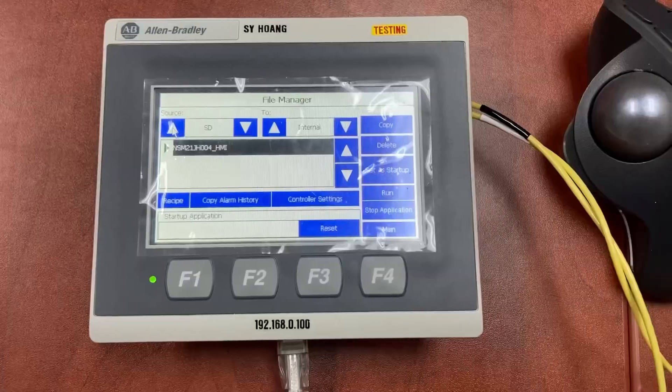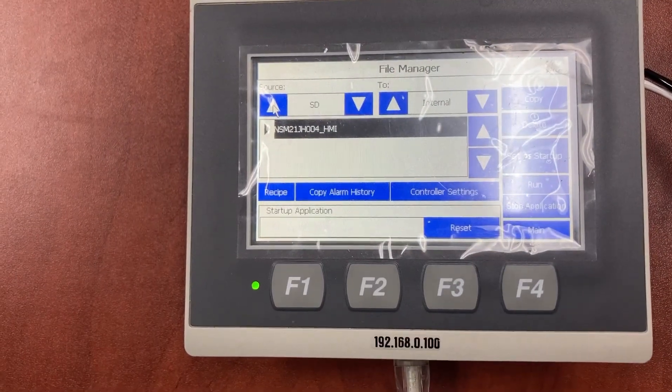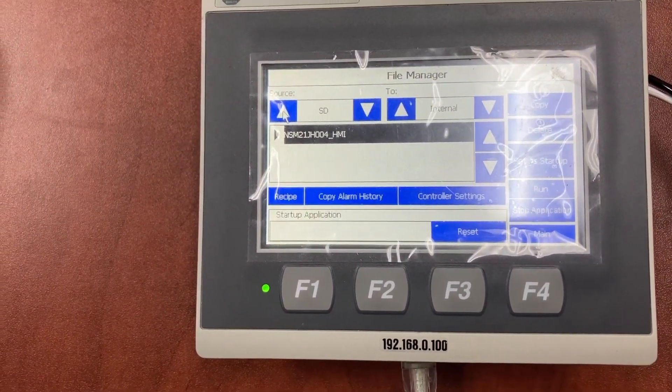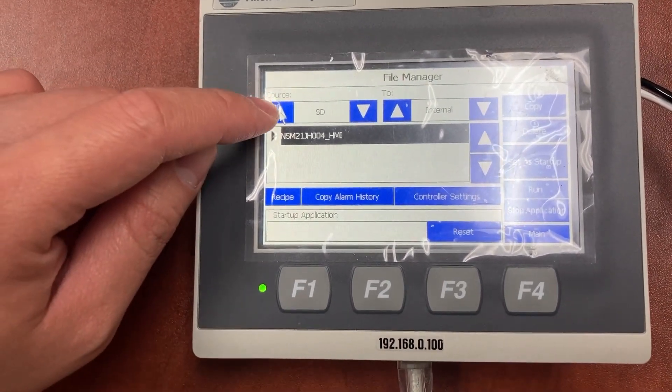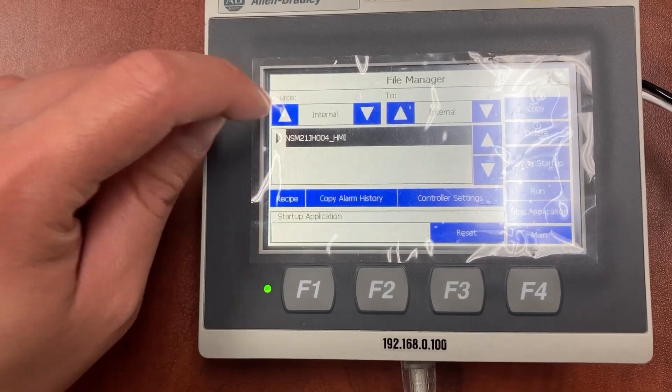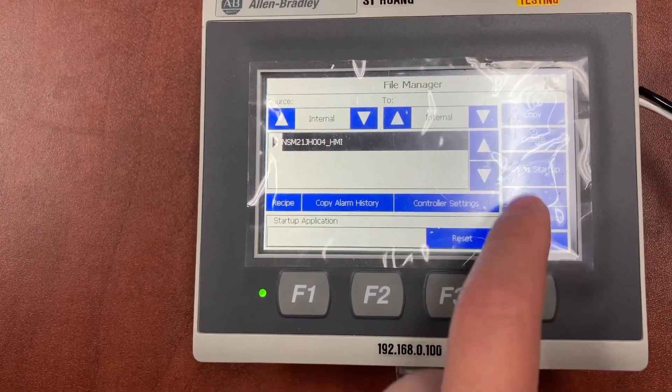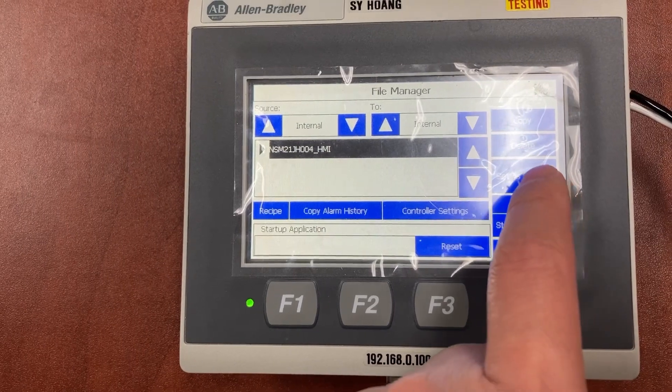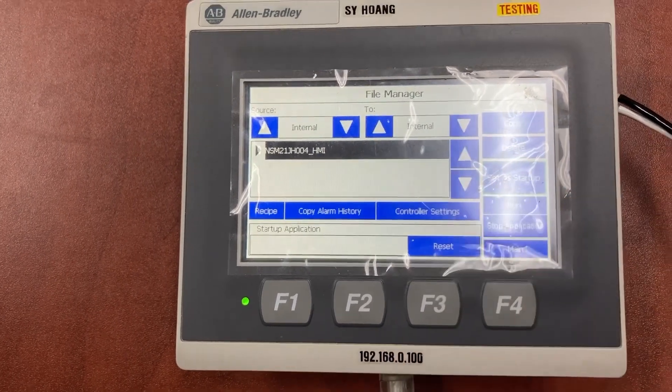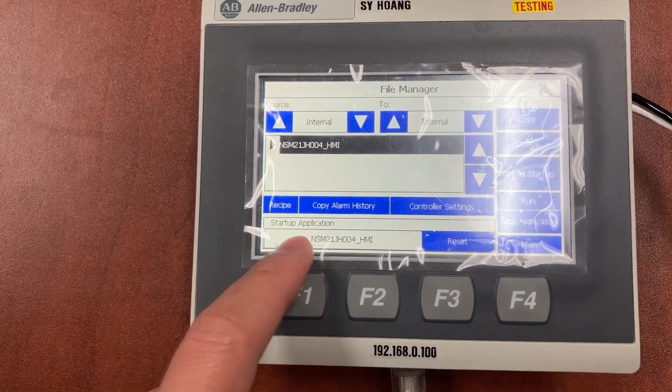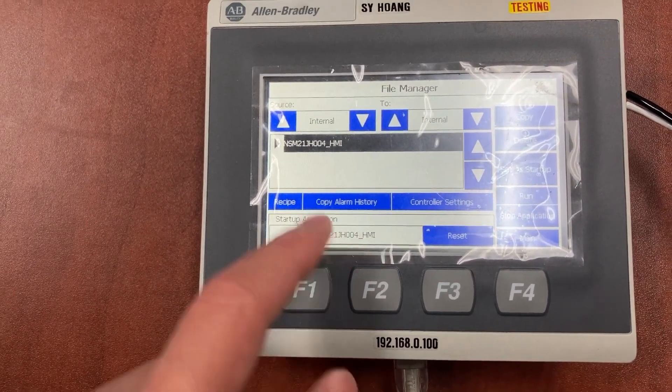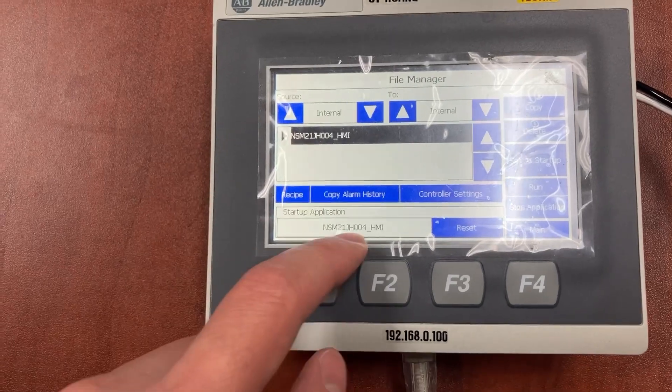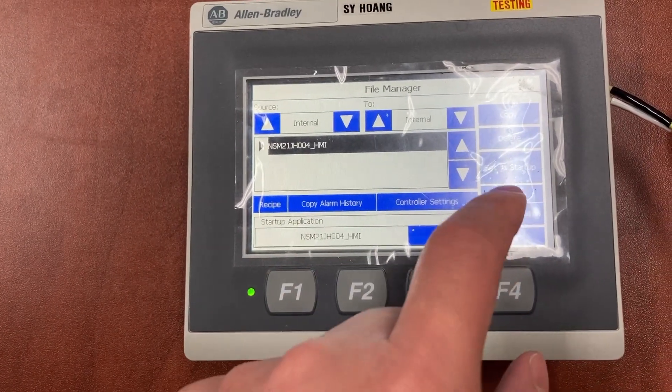After the HMI application was copied to the internal memory, we need to change source back to internal and set as startup. Startup application now is the one we just copied from the SD card.